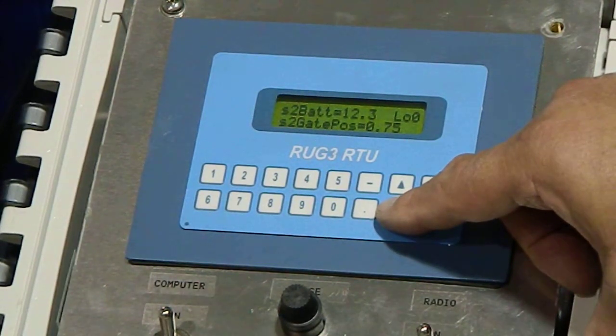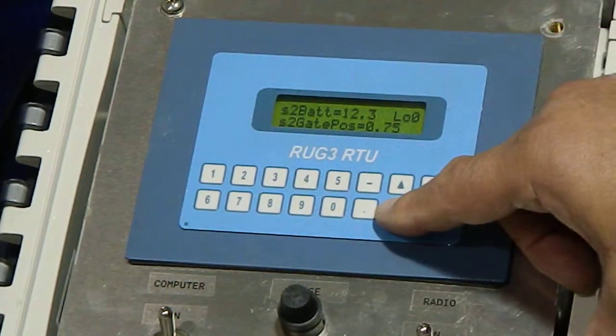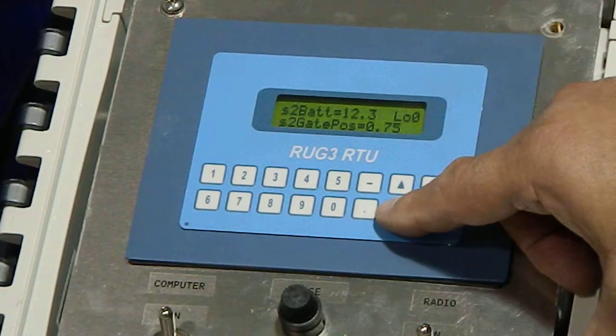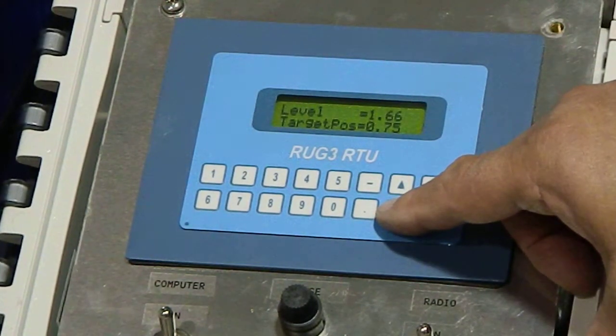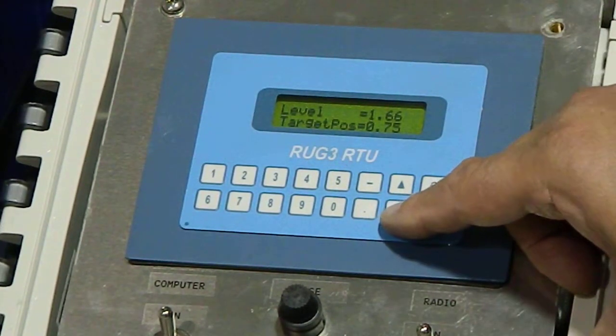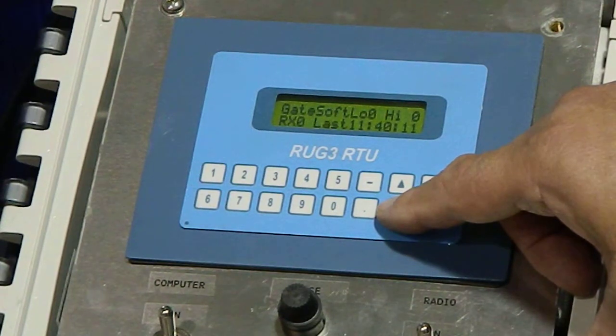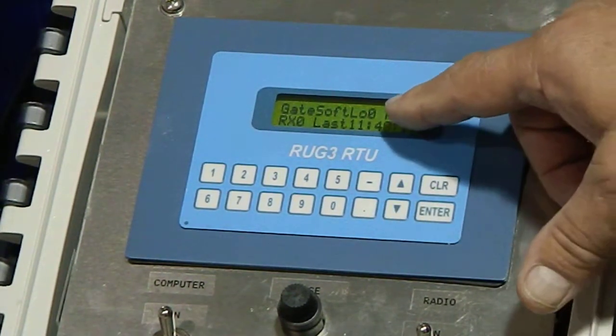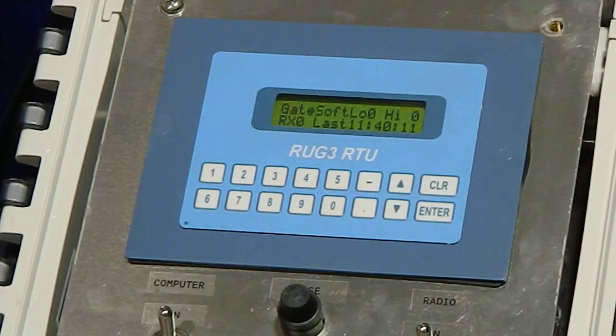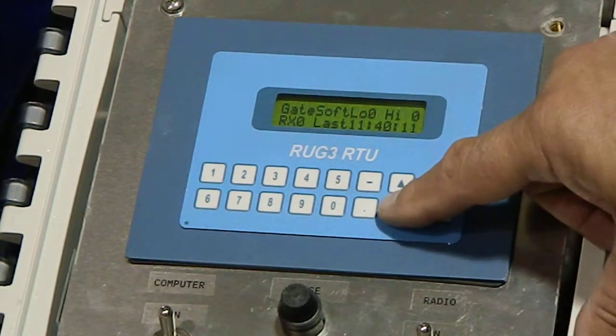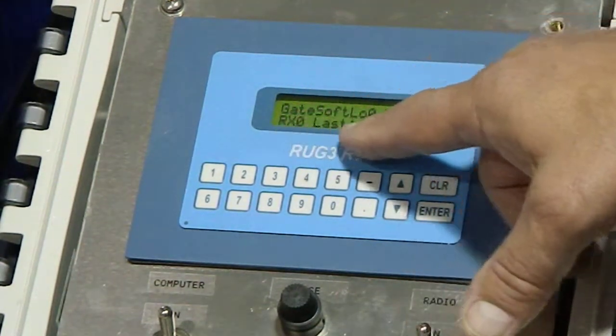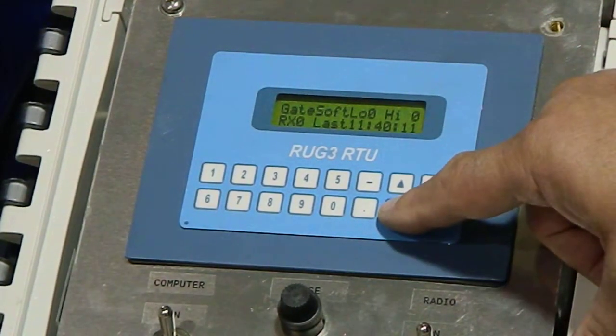It identifies the battery, the sensor number and the gate position that it's receiving from the slave, the level of the sensor that's attached to the slave unit, and then the target gate position. This also tells us whether the software limits, the low or high, are enabled in any way. In other words, has it hit the limit that it's supposed to be stopping at for any reason. And then it tells the last received transmission time that it received the signal.